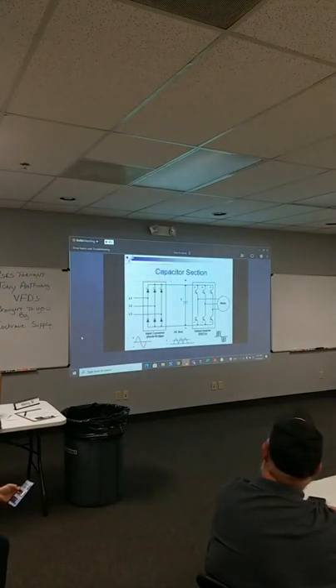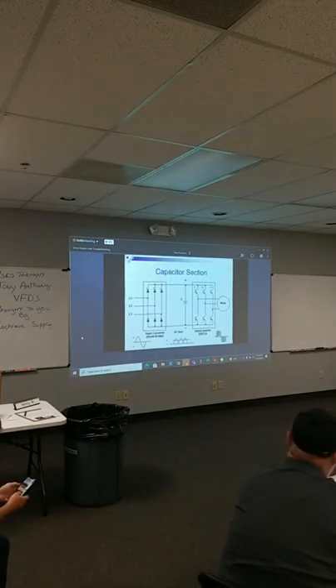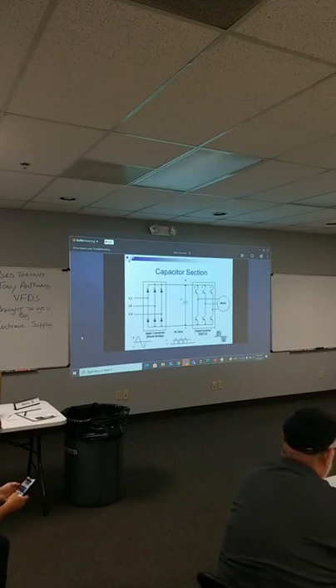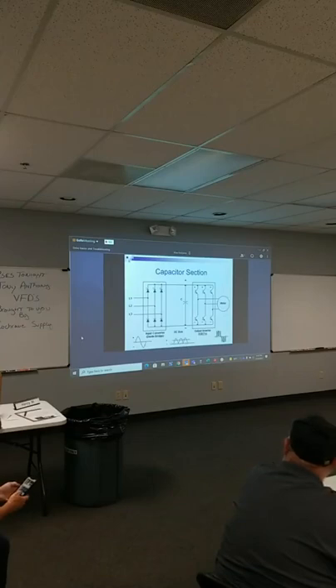Yes, it's inherent in how we create the DC bus. We're pulling power off the top. If you look at an AC sine wave, it shows in this picture right here at the bottom. We're only pulling power right off the peaks of the top and the bottom. Can you see my mouse? Right. And we're pulling it off the bottom here. So we're only pulling power from the peaks. And with the capacitor charging up, that creates the elevated voltage for the DC bus voltage. It's not the RMS, it's the peaks.